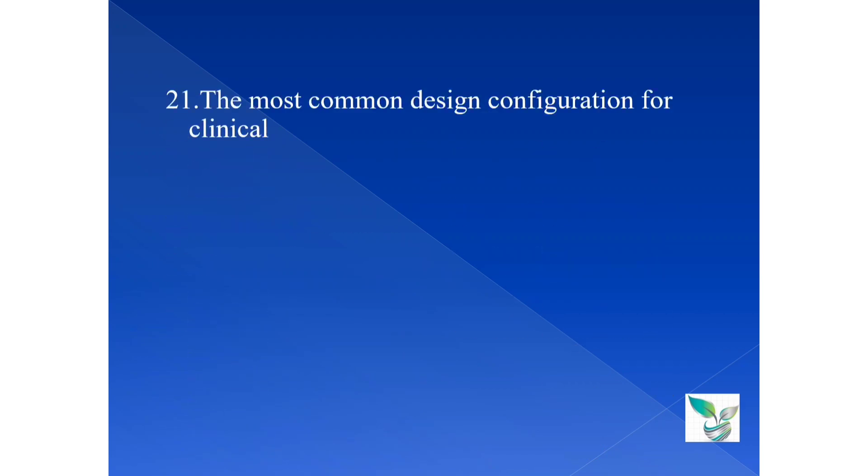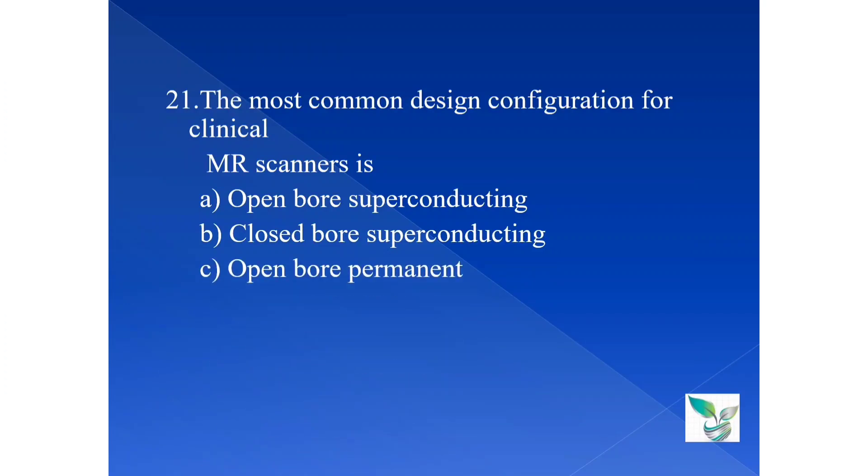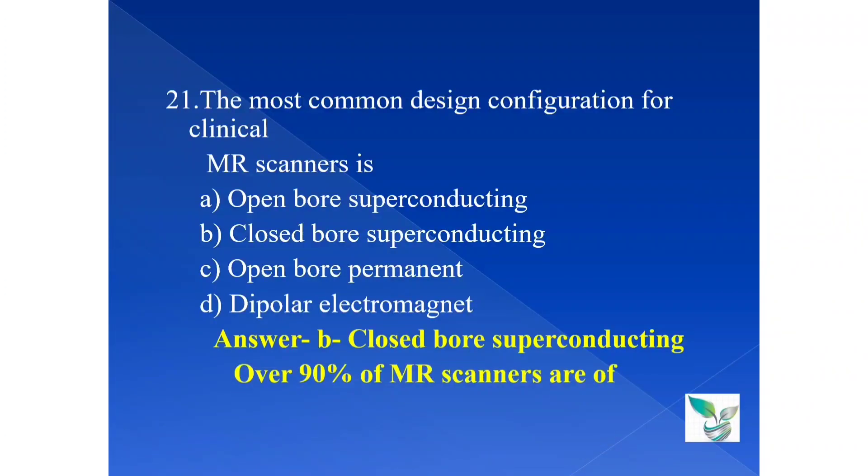Moving on to the 21st question. The most common design configuration for clinical MRI scanners is option A open bore superconducting, option B closed bore superconducting, option C open bore permanent and option D dipolar electromagnet. The answer is option B closed bore superconducting. So let us see the explanation. Over 90% of MRI scanners are of closed bore superconducting.